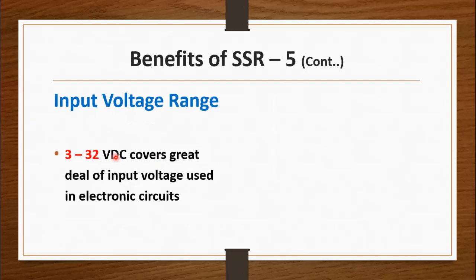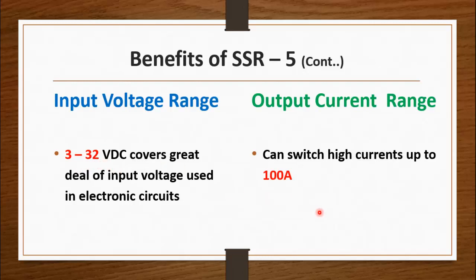The input voltage range of the SSR is quite wide — between 3 to 32 volt DC — so you don't have to change the relay model depending on your input voltage. You can use any voltage to energize this SSR. Also, the output current range of the solid state relay is very high, ranging up to 100 amperes. To drive such high-current loads you cannot find a normal electromagnetic relay — you would have to go for a contactor or some other mechanism.